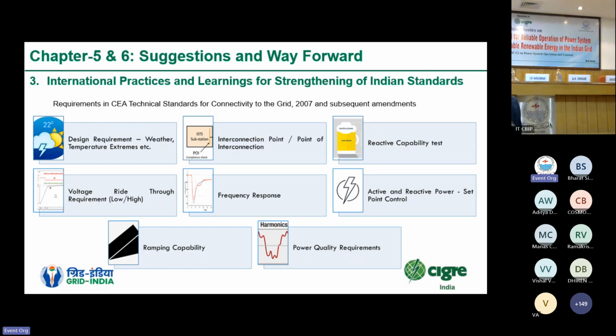So from international learnings and for the strengthening of Indian standards, a few requirements have been mentioned based on a literature survey of international best practices, like in the design requirements of the plants, for example the definition of the interconnection point, where all the compliances need to be at the point of interconnection. It is there in the standards. A detailed diagram with the labeling of the point of interconnection, which is there in other standards, could be given. Then there is reactive capability, and how it is specified in the different standards. What are the voltage ride-through requirements? There are more detailed, elaborate voltage ride-through requirements in other international standards, and ramping requirements as well as power quality requirements are also in detail.